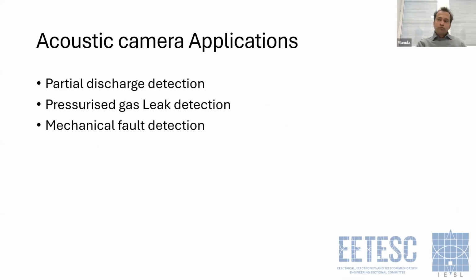Okay, so now we know what an ultrasound camera is. Then let's go to ultrasound camera applications one by one. Basically there are 3 types of applications that are commonly used for this kind of ultrasound camera. The first one is partial discharge detection, then pressurized gas leak detection, and also mechanical fault detection.